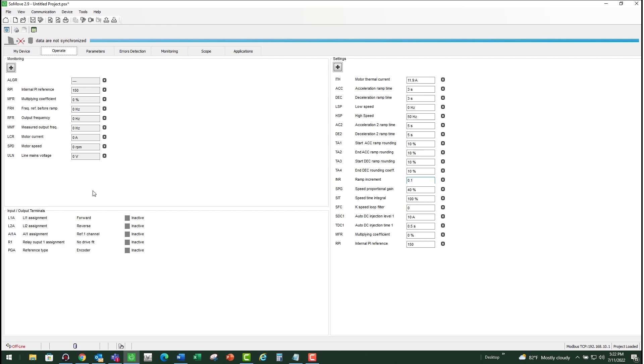In the second scenario, if the VFD is tripping during normal running speed, then you need to make sure you monitor the voltages for surges and spikes. If you have any surge or spike, any incoming surge or spike on your line side, that will cause it to trip. Look at maybe adding a line reactor or a surge suppressor if you want to avoid that trip.